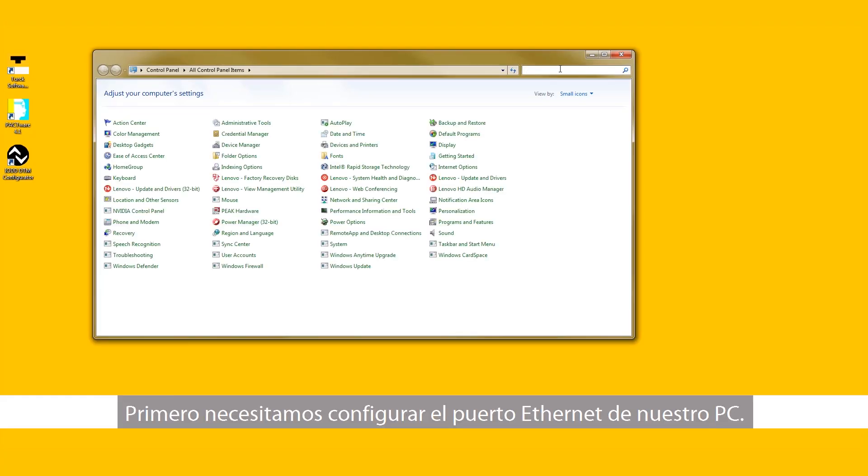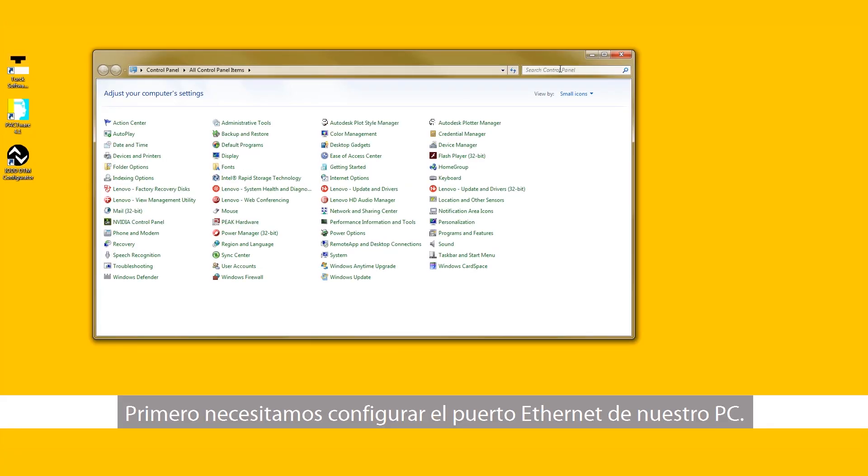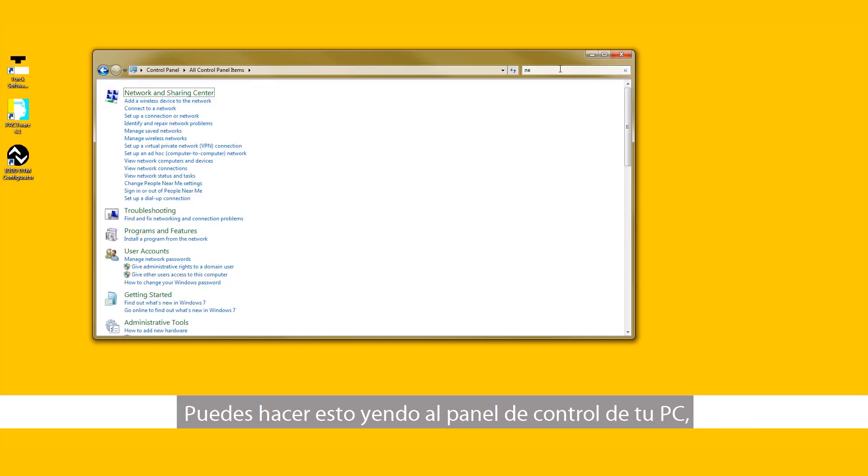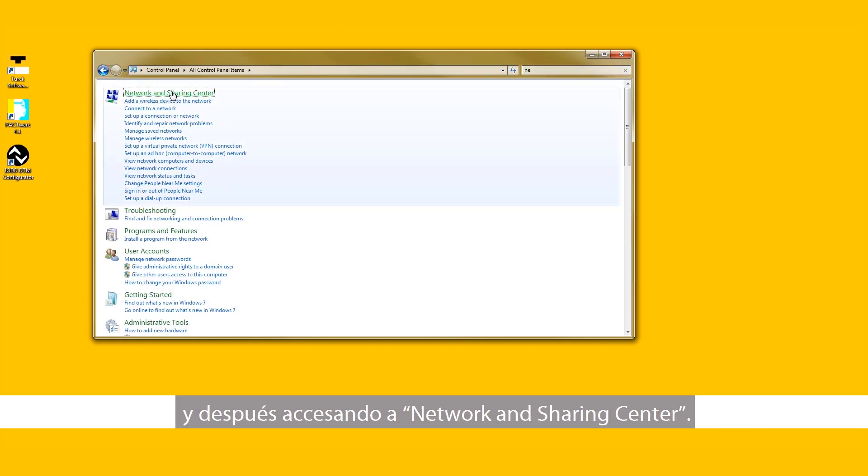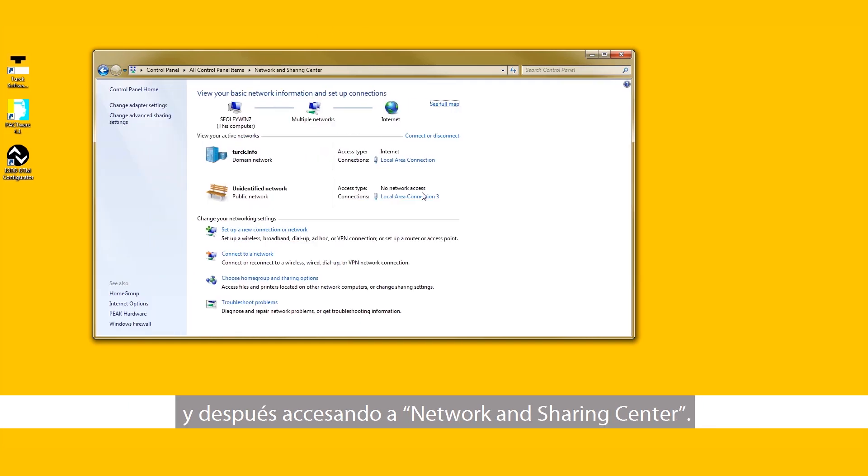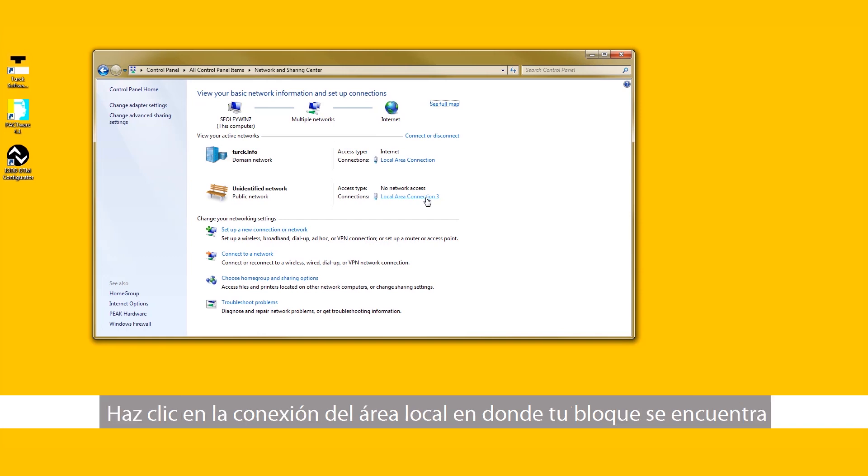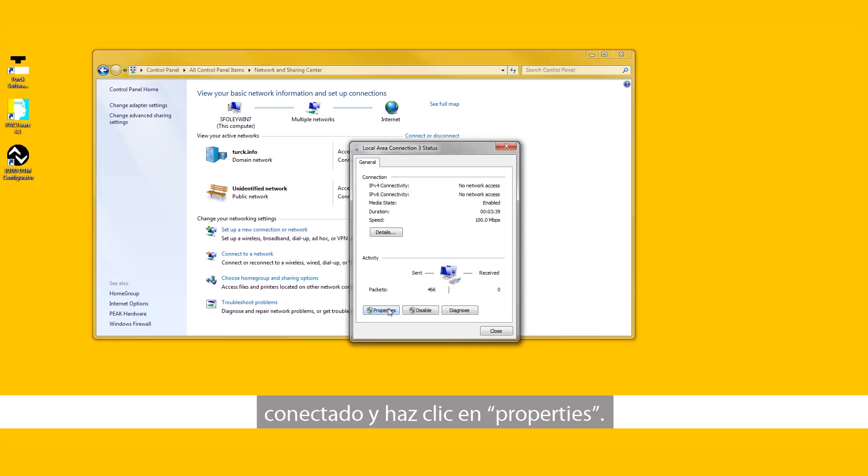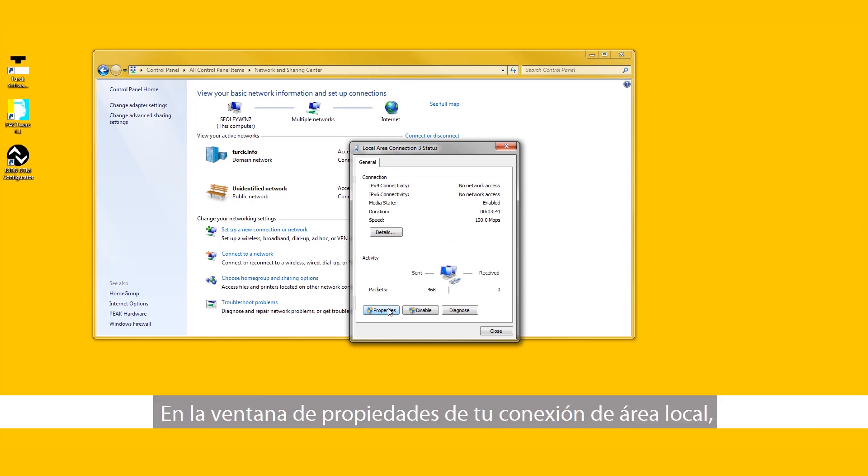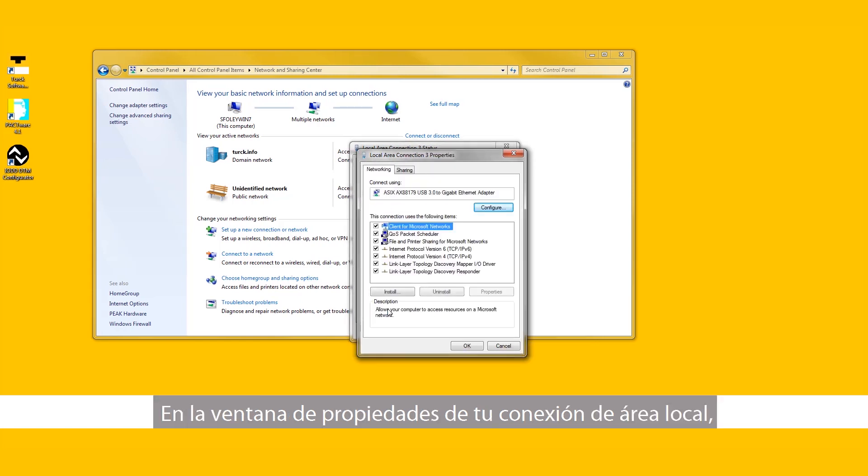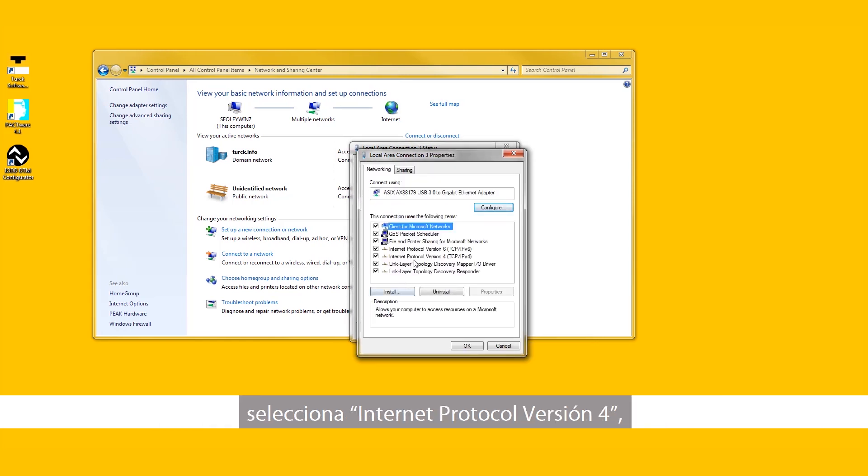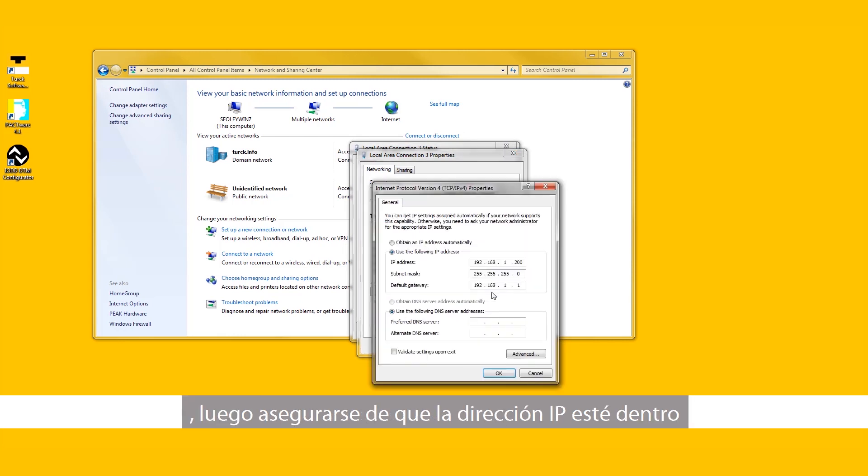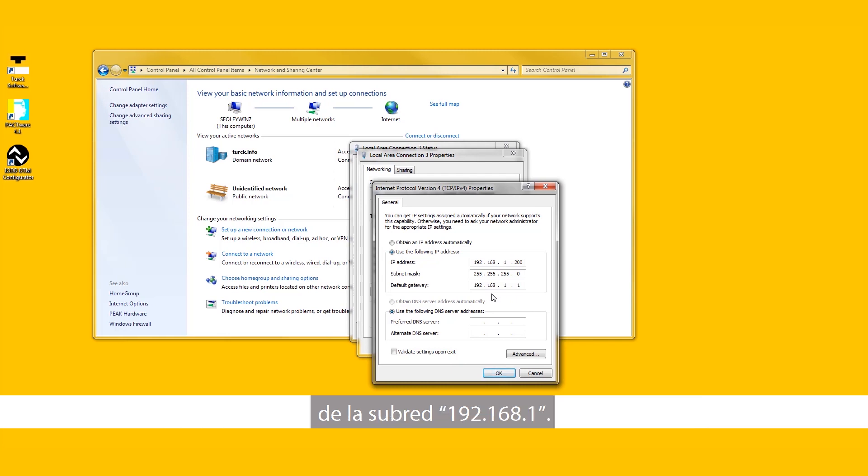We first need to configure the Ethernet port on the PC. You can do this by going to the control panel on your PC and then accessing Network and Sharing Center. Click on the local area connection your block is plugged into and click Properties. In the Local Area Connection Properties window, select Internet Protocol Version 4 and then select Properties. Ensure the IP address is within the 192.168.1 subnet.